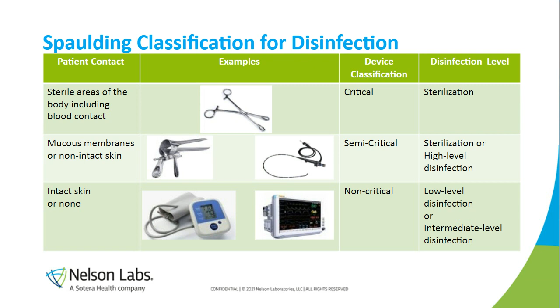However, there is a large hazy gray area in determining which non-critical devices needed intermediate-level disinfection or low-level disinfection. The new update to TIR12 changed the focus from contact to the patient to the risk of infection to the patient. If a device can be soiled with blood or other potentially infectious materials, then at minimum the device should undergo an intermediate level disinfection.